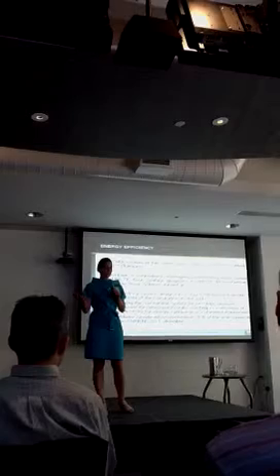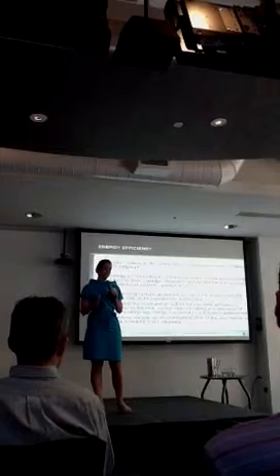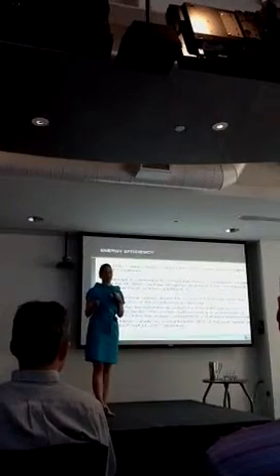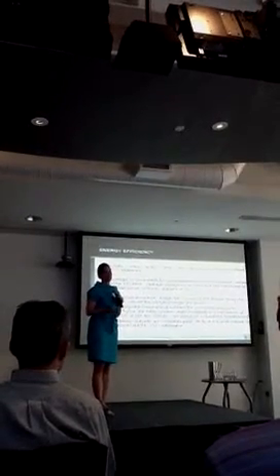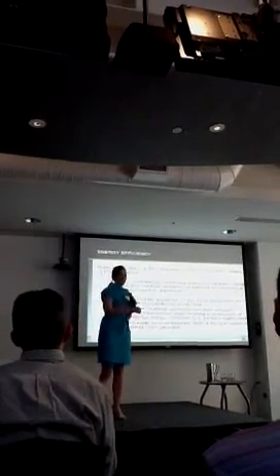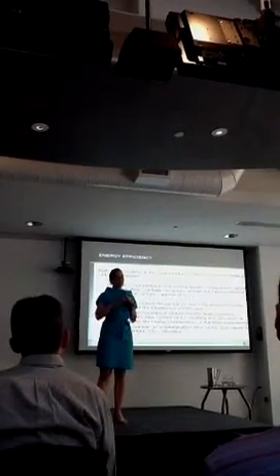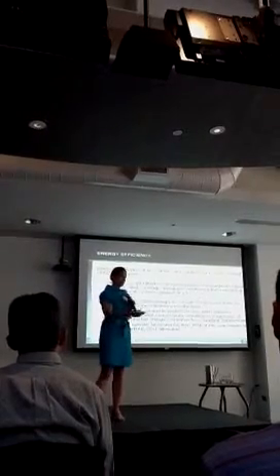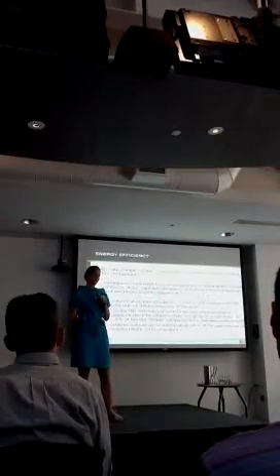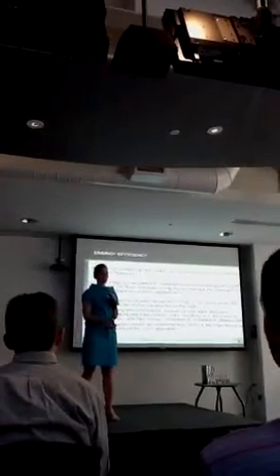So Vantage has really committed itself to being LEED Platinum on all of its data centers, as well as minimizing that. So we hired HPEYP to audit our PUE, and we came up with an annualized value of 1.12, which means 12% of the energy that's supplied to the building on the line side of the transformer is actually lost. Most data centers, as John mentioned earlier, is 1.7. So we're really getting all of the power we possibly can to the services that we're trying to support. That saves money as well as minimizes the amount of resources that we're using.